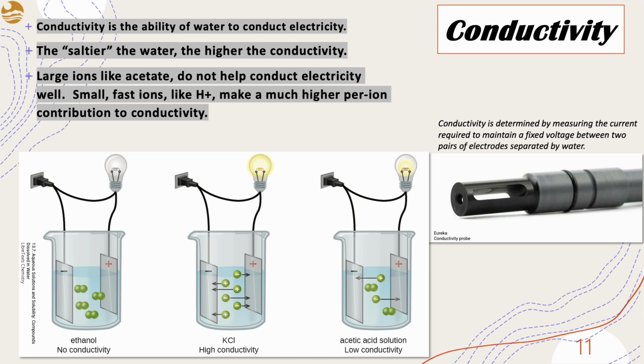The conductivity sensor in the data sonde is a 4-electrode sensor, operated by measuring the current required to maintain a fixed voltage between two pairs of electrodes separated by the water. The conductivity probe is calibrated with one standard, which is a solution with a known concentration of potassium chloride.